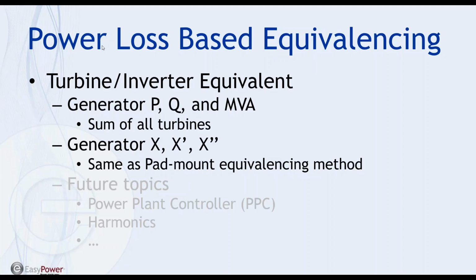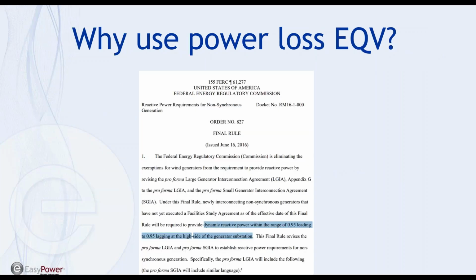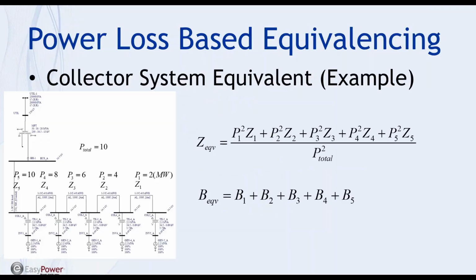Now, some people may ask why we use this power loss-based method, why we do not use Thevenin equivalent, right? I stopped myself from saying Thevenin throughout the presentation just to avoid confusion, because some people use Thevenin equivalent. My takeaway on this method is as follows. It's because FERC has an order, FERC Order 827, stating that any non-synchronous generation needs to provide dynamic reactive power within the range of 0.95 lead and lag at the high side of the generator substation. What does that mean? That means if you have a certain amount of inverters generating, let's say, 10 megawatt at the terminal of the inverter, what the utility company, FERC and those regulatory entities care about is what you can provide at the point of interconnection.